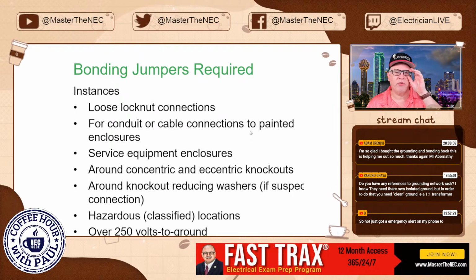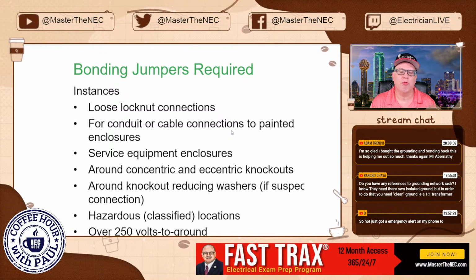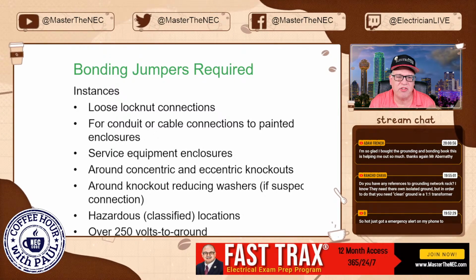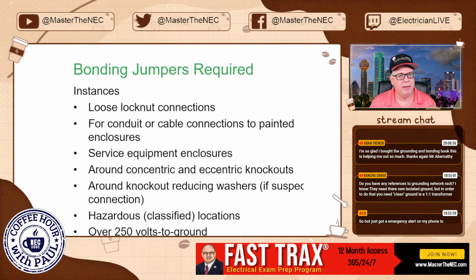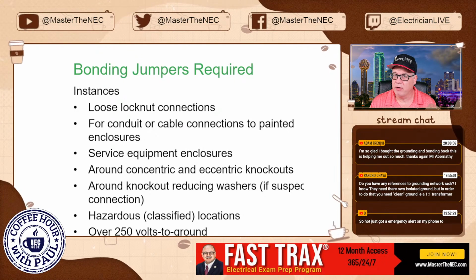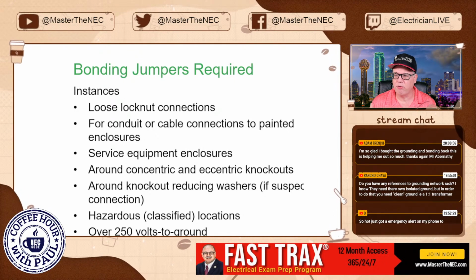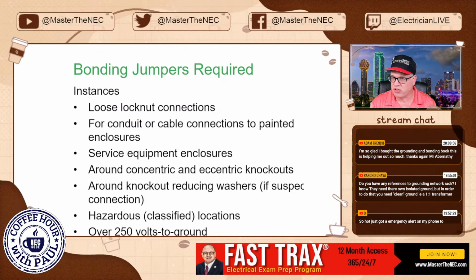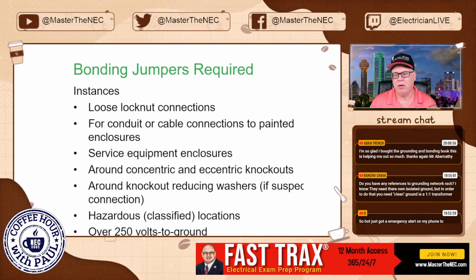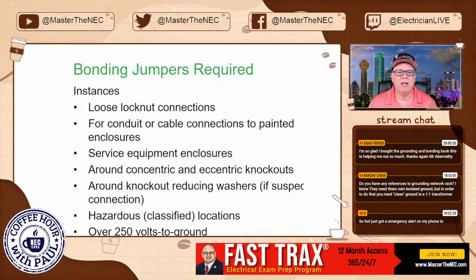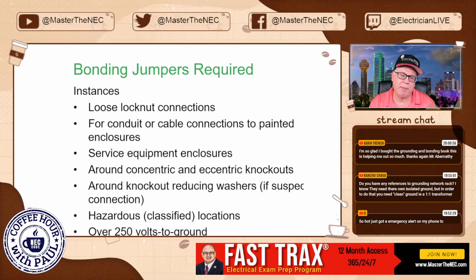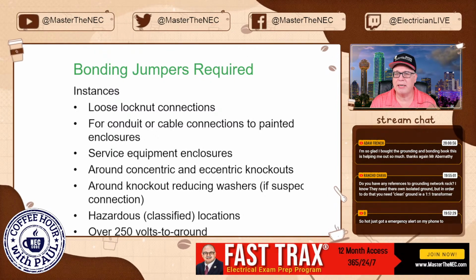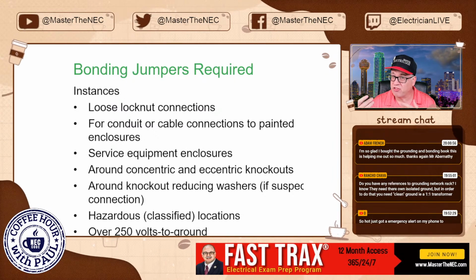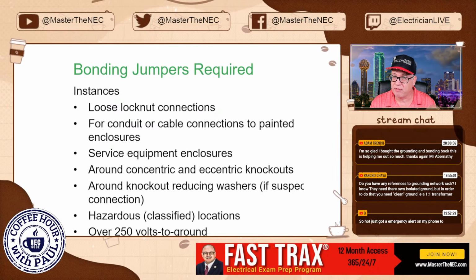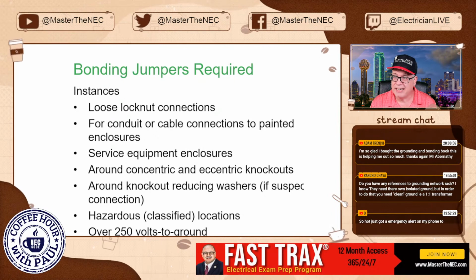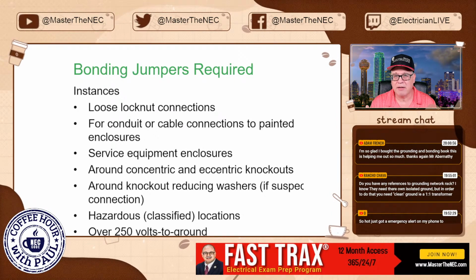Now, bonding jumpers, when is a bonding jumper required? That's another question I get quite a bit. Now, when you're looking at services, for example, and you're looking at 250.90 and 250.92, it becomes very evident when you would need a bonding jumper. But let's just look at some instances where bonding jumpers would be critically important to that what? Establishing that effective low impedance ground fault current path and keep the system intact, okay?